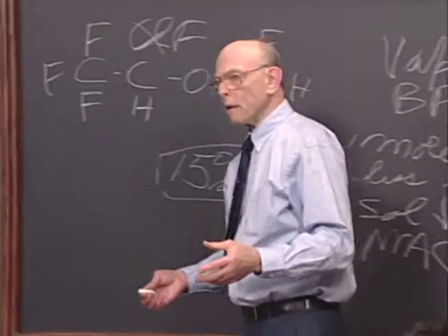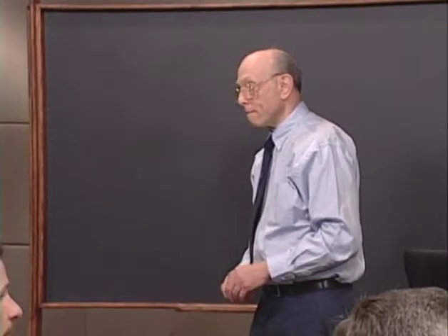How can we get drying of the absorbent? How can that be? It's sitting in that closed container. Let's see, who haven't we called on? Gentleman with the orange tie. Well, you get drying of the absorbent if you have high gas flow rates touching the absorbent for an extended period of time. Right. So if you give an anesthetic and at the end you turn off the oxygen, there's no problem. But if you leave it on and you go away for the weekend, there may be a problem. What else do you have to do besides leave the flow on in order to get drying? Well, there has to be actual contact with the absorbent by the flow.